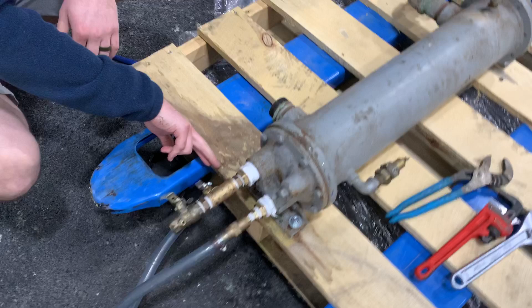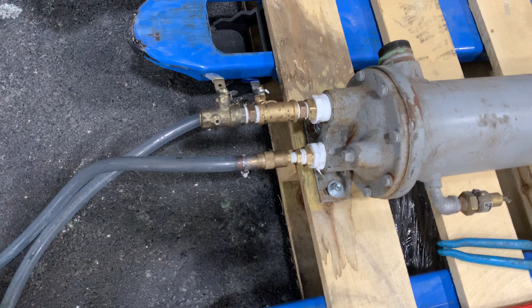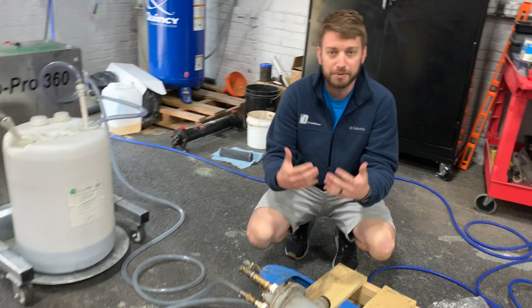This allows you to flush while the heat exchanger is on your actual press. That way your maintenance team doesn't have to spend, whether it's a half hour or 2 hours, pulling it off of the machine. You can simply build it into your preventative maintenance program - hey, if your heat exchanger goes down every 14 months, maybe every 8 months, you just plumb in and do a quick flushing for a half hour every so often.